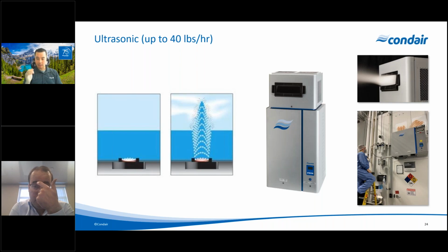We take that mist, and on top of that unit you can see we have a blower or fan pack that takes the mist and blows it directly into the space. It's very critical that you use RO or DI water, because if you put potable water through the system, the transducers will clog up and you'll lose capacity and have more maintenance. These are in-space units only, so we don't have the ability to put these in duct. In terms of capacity, they start at about 20 pounds an hour up to about 40 pounds an hour as the maximum high-end capacity for a single unit.